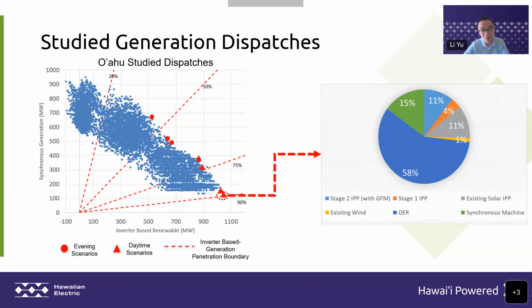An example of a generation profile in one of these studied dispatches is shown on the right side of the slide. This one is a dispatch with very high generation from inverter-based resources. We can see around 58% of the generation coming from the distribution level, the DER side, and the system only has 15% of the generation from rotating machines. The remaining part is from wind, existing solar, stage 1 procurement projects, which can only do GFL so far, and then stage 2 GFM projects.